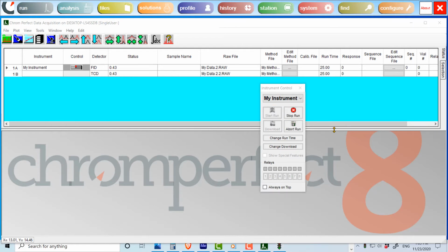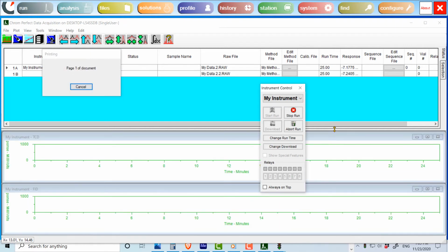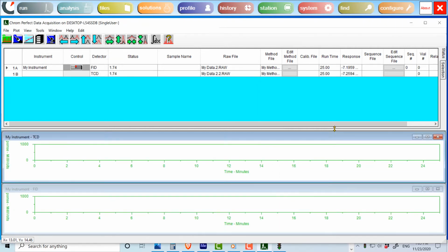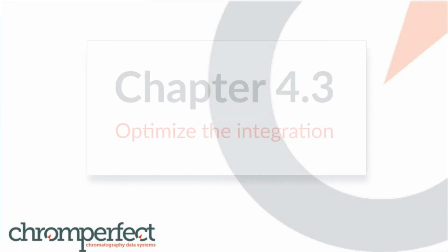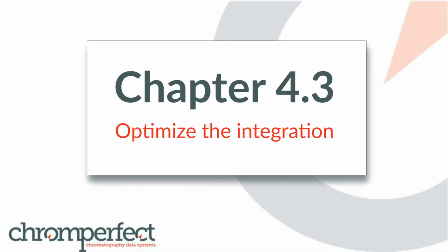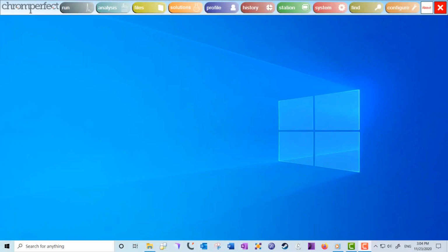Proceed to collect runs until you have at least one good data file, in which all the peaks of interest are well separated and exhibit their proper retention times. Optimize the integration. Now that we have one or more data files to work with, we may optimize the method file. There are two tasks before us: to verify that the sampling rate is correct and to set the integration parameters. We will do this by using the analysis program, which will soon become familiar to you.